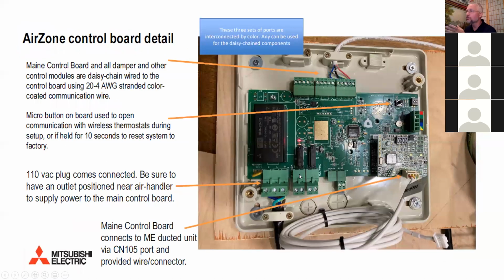A little bit closer picture of the control board. Here are those daisy chain connectors. It comes with a 110 plug, so you've got to park it near an outlet wherever you're going to have this parked. Typically, it's in the same space as the air handler. Here's your CN105 connector plugging into the Mitsubishi communicator card that plugs onto the standard AirZone card. That's just kind of demystifying it.